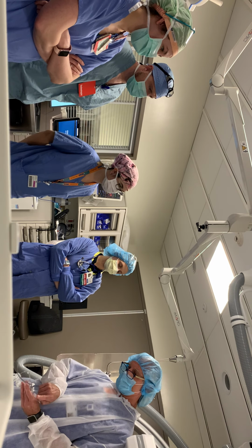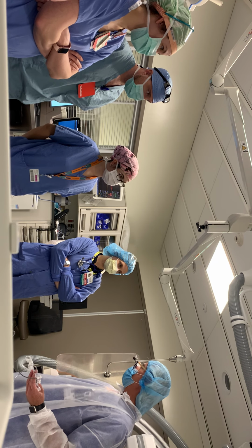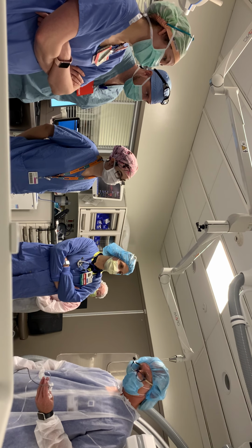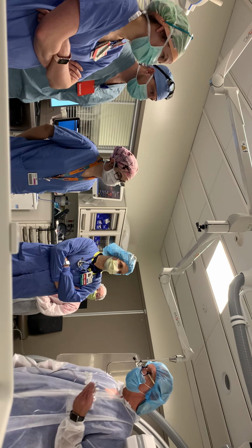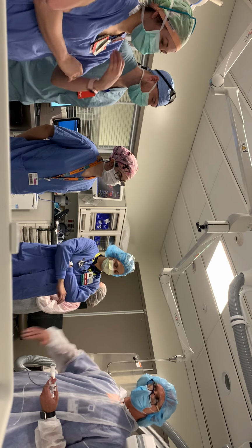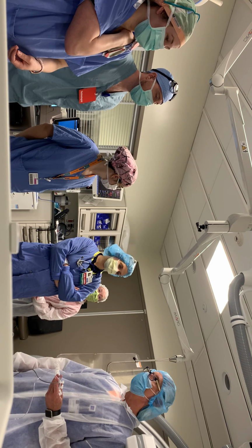Another thing, same thing sort of that happens, is that they want to check their zero. They don't want to re-zero, but they want to check it. So they'll open, they're not attached to anything. And they're open and they'll look up and they're thinking, well, this should go back to zero, right? It won't, because it's sensing the weight of the fluid here. And depending on where this is, that line is either going to be above or below your zero point. So your knowledge of that will help them to understand that that's not how you check zero.